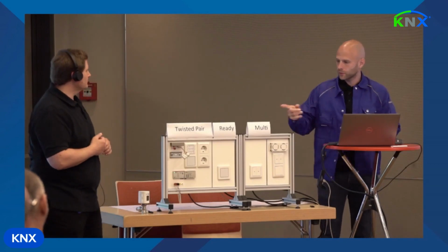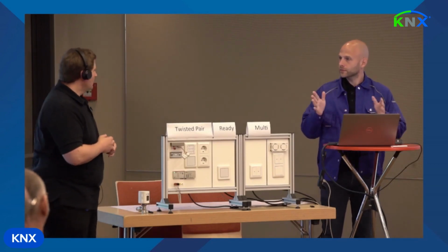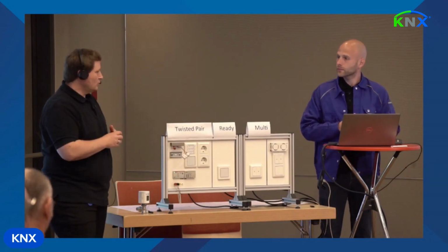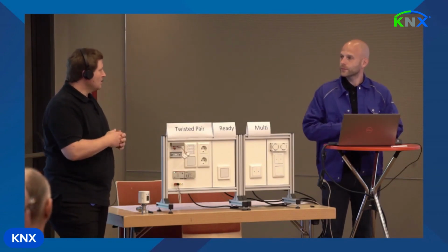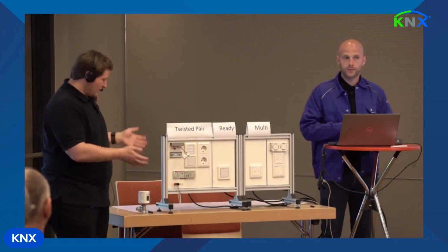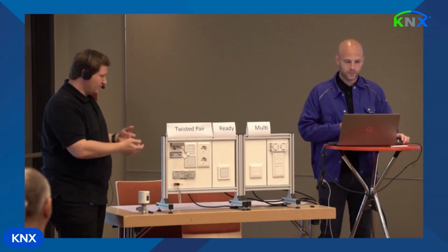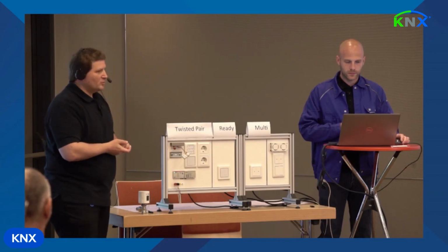This is the 500 millisecond preamble. Exactly. It waits, that it checks. ETS first tried if the device would already be in listening mode. Yeah. And after the timeout, okay, this device is not in listening mode. It sent out the wake up frames and waited until the device said that it's ready to be programmed.